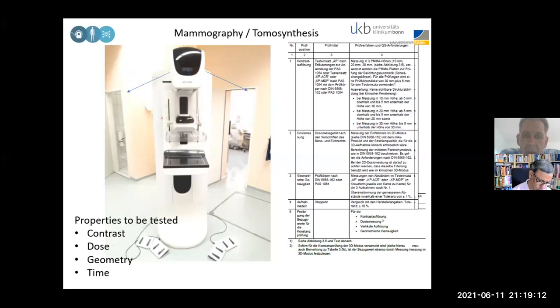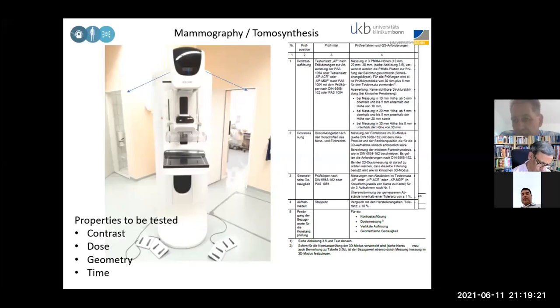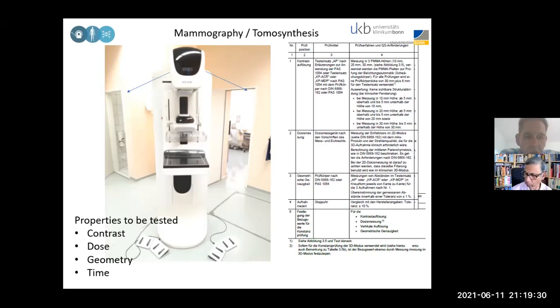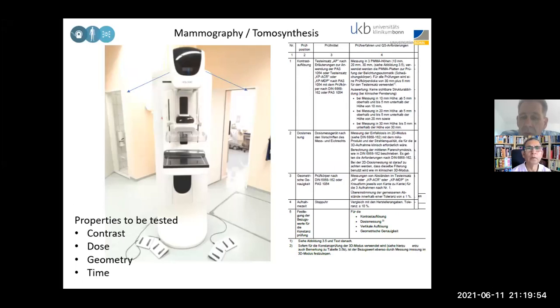Here you see tomosynthesis mammography. This is a mammography machine which has the capability to move the head around the breast, so you get a 3D image of the breast. What do we test with this machine? On the left-hand side is the German legislation, don't try to read it, it's German. I have the excerpt on the left-hand side. It is contrast, dose, geometry, and time. Those are the four properties which are tested for this device: contrast, dose, geometry, and time.